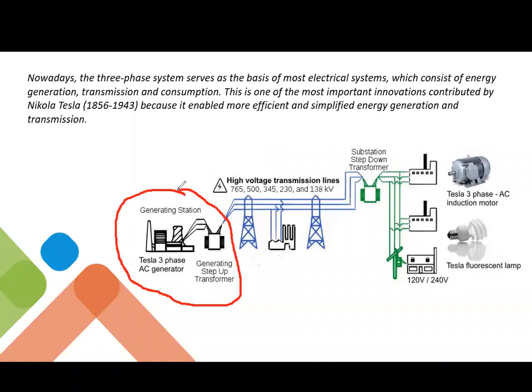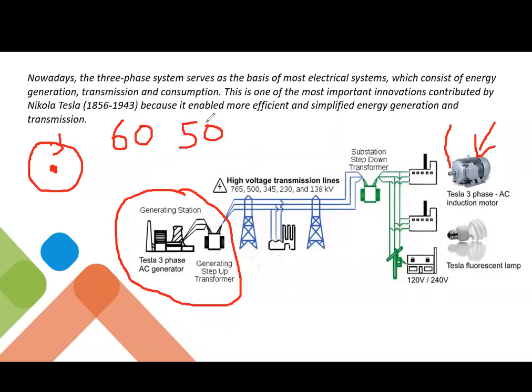Tesla was the first person to understand that, especially in a three phase motor, we would have a rotating magnetic field inside there and allow those three phases to give us some mechanical power at the end of this shaft right out here. They had to make some decisions back then, right? They had to make a decision on frequency. They decided that 60 hertz was the way for us to go. What we should understand is the Germans were doing the exact same thing at the exact same time, and the Germans decided that 50 hertz was better for them. It ended up in a dead heat, so we stayed with our 60 and they stayed with their 50. And that's probably the way it's going to be for a while.